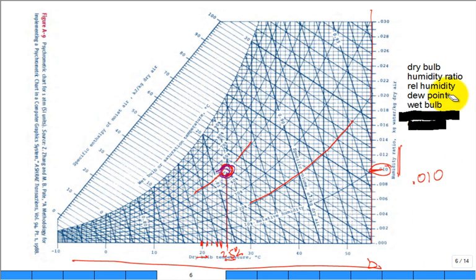The wet bulb is the next temperature, and it's along these sloped lines — that's going to be a constant enthalpy line. You project up until you get to that point and then read off the temperature for the wet bulb. For 25°C at 50% relative humidity, what is the wet bulb temperature? Around 16–17°C.